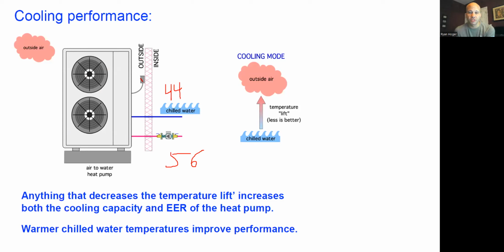And just like in the previous discussion, we have this term called lift, which is the temperature difference between the water and the outdoor air. The smaller that lift is, the easier it is for me to get the desired temperature you want, and the more cost effective it is, right? For example, if I want 44-degree water inside, and it happens to be 50 degrees outside, it's pretty easy to make 44-degree water with 50-degree air. But if it's 80 degrees outside, it becomes a little more hard. And if it's 100 degrees outside, it becomes very hard to do that. So same kind of idea that we had before. The closer the outdoor temp is to the water temperature, the better.